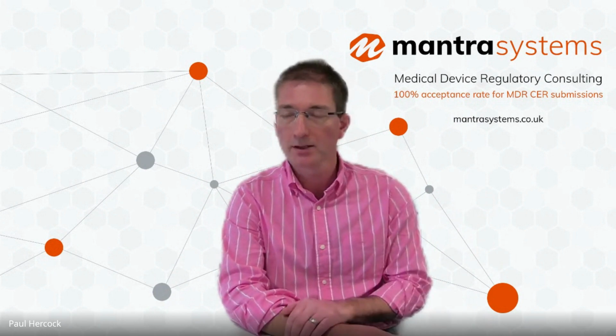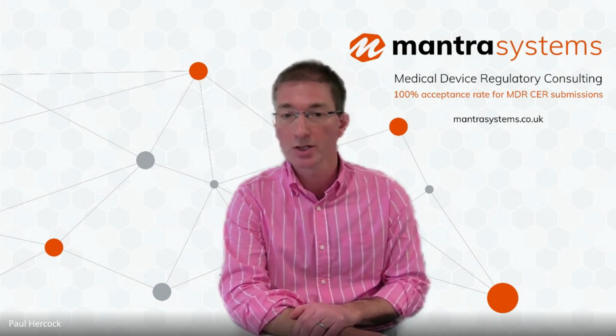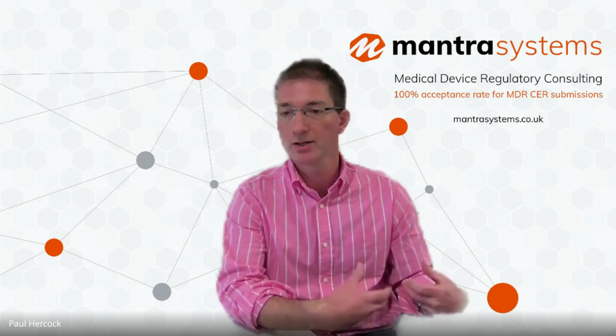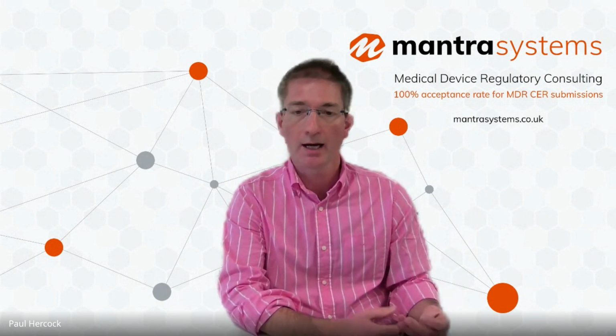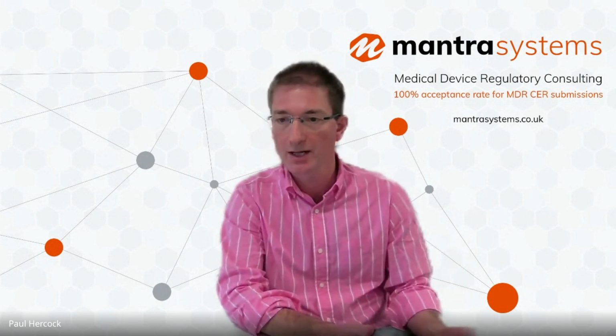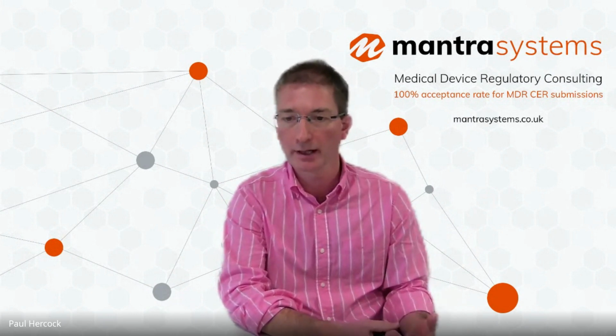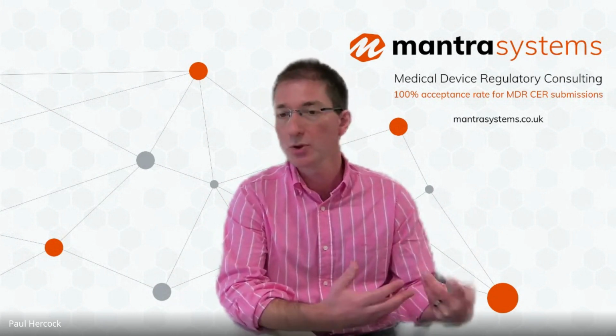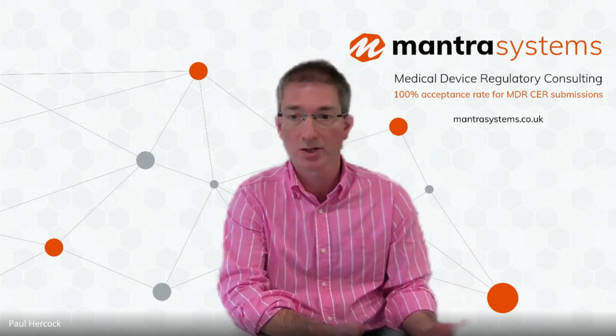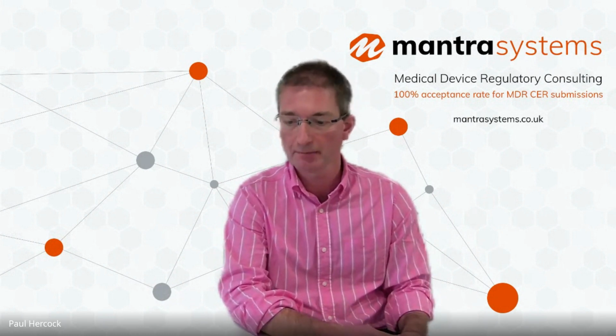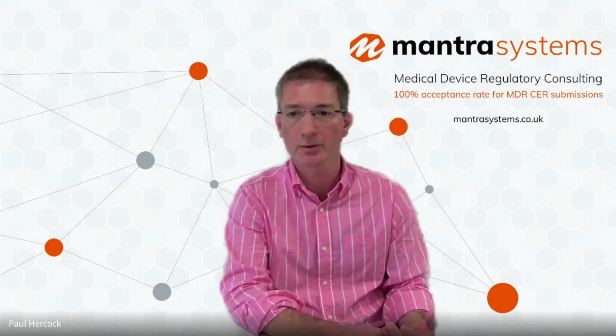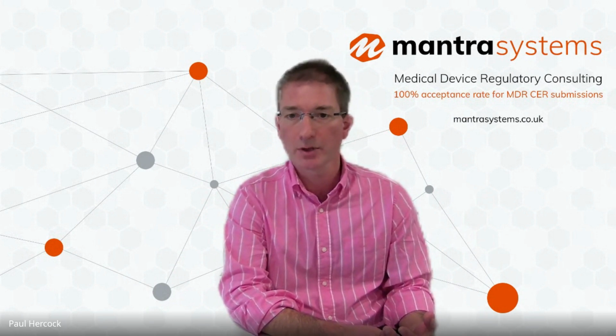Next, I would recommend an important section, scope of the clinical evaluation. This is where you set out what the device is and what hypothesis you're testing. What are you going to look at through the clinical evaluation? It's also where you set out alternatives to the subject device, similar devices, and so on. The next section I would recommend, this is in line with some of the recommendations from MDCG.